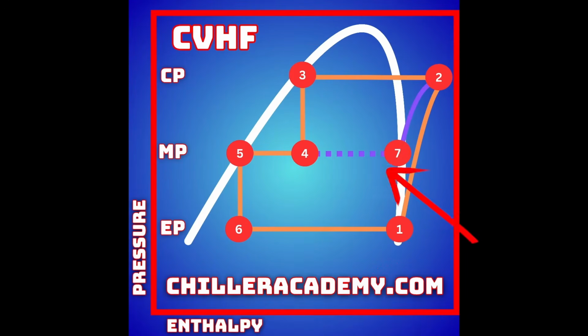This white line shows the saturation curve the refrigerant is operating within. This is a basic enthalpy chart. When you see a saturation chart for refrigerants, you see these curves. It's showing you the enthalpy cycle of that refrigerant, or the saturation cycle. Now, let me explain what's happening here so that we get a concept of where we are. Our liquid refrigerant, as we come in, so let's start with point number 1. I think that will be easier to follow.